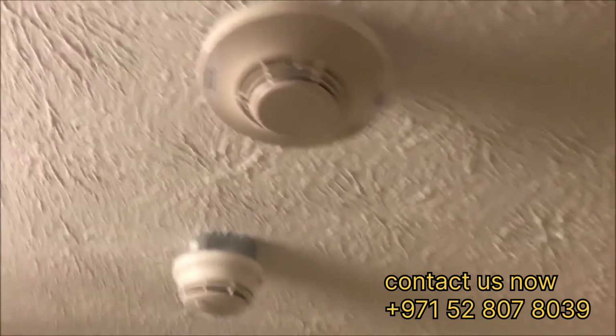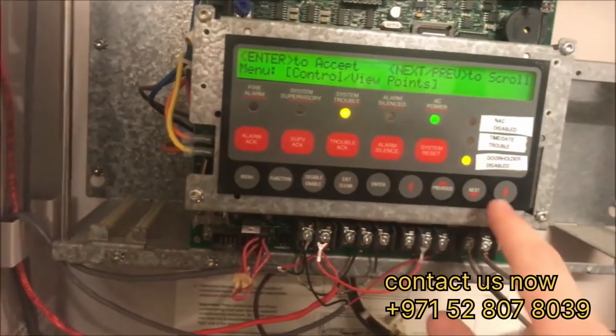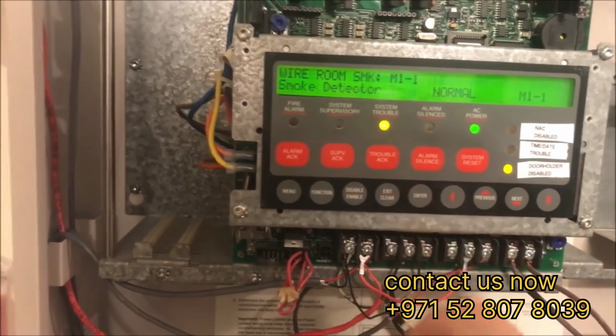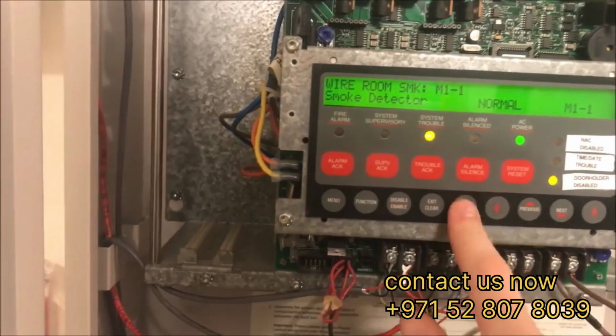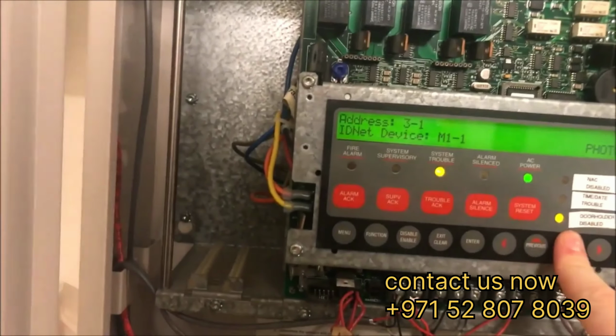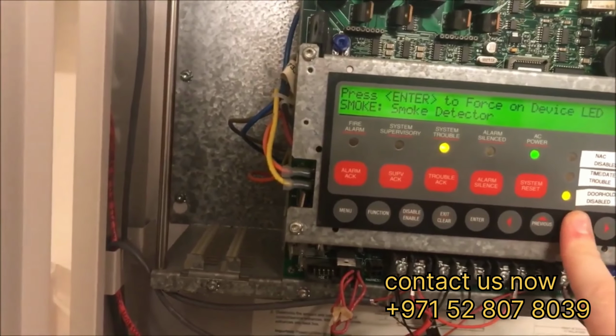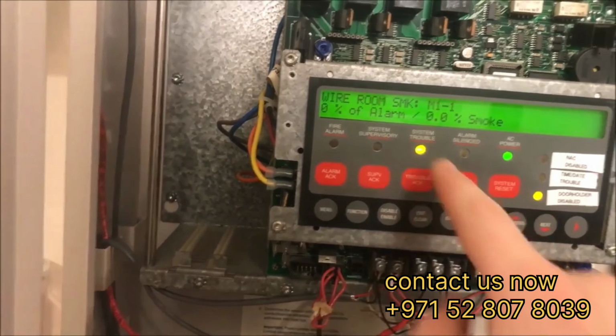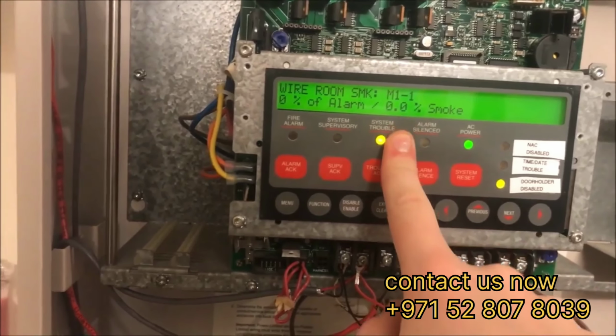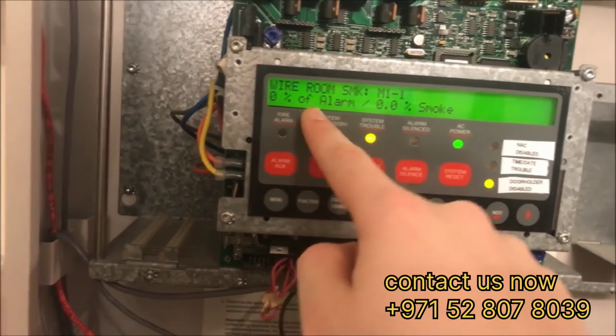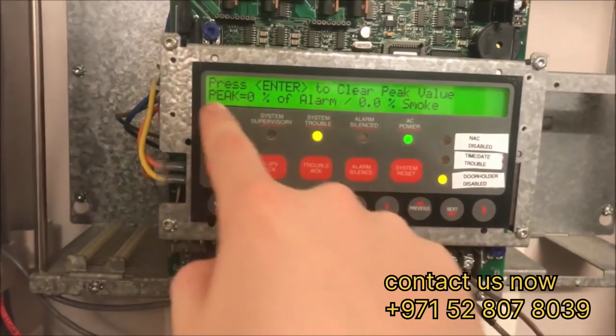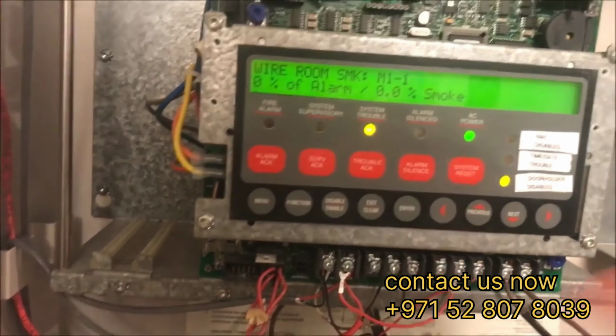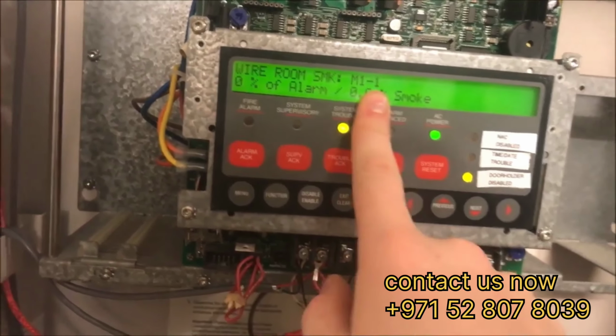In terms of a smoke detector, we're going to go in on my Simplex panel here. You can actually go in and see the current status of any point. So if I go into, I am talking to the smoke detector in the back room, I can scroll and you can see there is 0% smoke concentration in it, and we are at 0% of alarm threshold. And it will tell you your peak, like how high the smoke got. So you can see it has 0% in it.